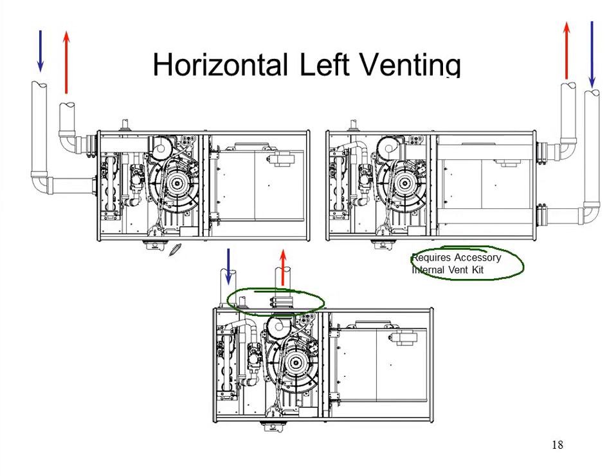You will also notice when you lay this thing on its side, that collector box that used to be over here now has to be located over here, and it's going to penetrate below the cabinet a little bit. So just keep that in mind when you're installing it, that this furnace can't be laying flat on the ground. It's going to have to be on little blocks or something like that in order to keep it elevated so the condensate trap can be on the bottom, right, because water has to flow down.